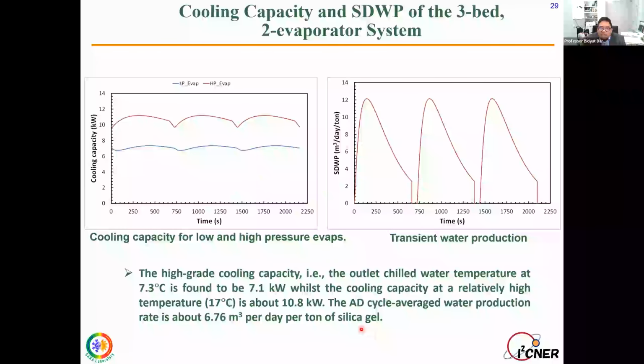And then if we see the cooling capacity, this is from our low pressure side, and this is the cooling capacity from our high pressure side. The high grade cooling capacity, that is at an outlet chilled water temperature of 7.3 degrees centigrade, is found to be 7.1 kilowatt, while the cooling capacity at a relatively high temperature of 17.3 degrees centigrade is about 10.8 kilowatt. For the adsorption cycle's average water production, this is our specific daily water production, in cubic meters of water per day per ton of silica gel, and it is about 6.76 cubic meters per day per ton of silica gel.